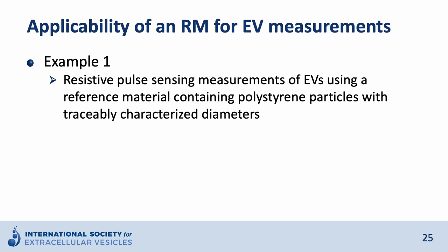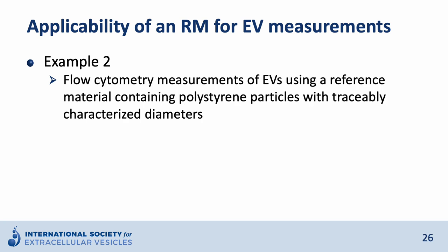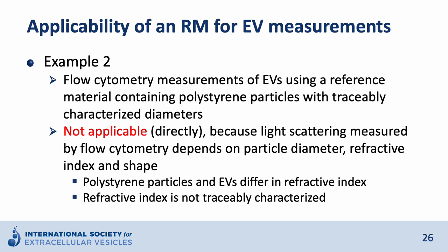The first example is measurement of EV size by resistive pulse sensing using polystyrene particles to calibrate the RPS measurement. This is applicable because the pulse height in RPS depends on the particle volume, which is defined for the polystyrene particles. The second example is flow cytometry analysis of EVs using polystyrene reference particles to obtain the diameter of the vesicles. This is not directly applicable because in flow cytometry, light scattering depends on many parameters including the particle diameter, the refractive index, and the shape. Polystyrene particles and EVs differ in refractive index, and the refractive index of the polystyrene particle standard is not traceably characterized.